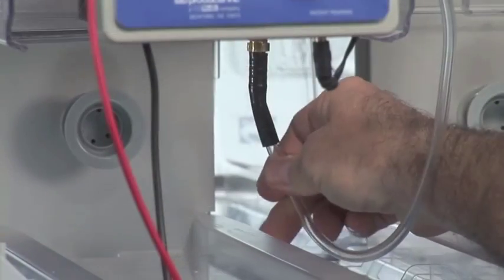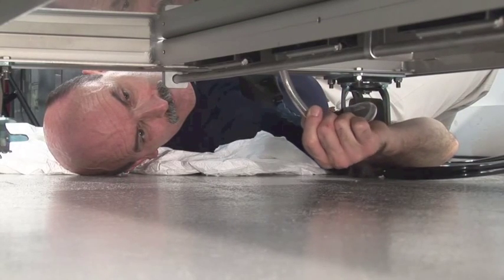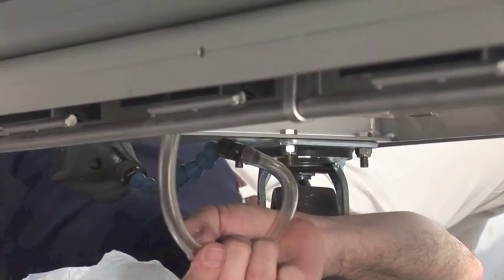and the gasket seal. If there was a leak, it would migrate along that U-channel. And I got underneath and checked all eight seals and scanned that entire channel, and I found nothing. It stayed on zeroes. Had anything leaked even from the docking seals and had dropped along the structure of the unit, it would have collected at that point, at the bottom, in between the cages. It's just the natural point, given the design of the unit, and there was nothing there.